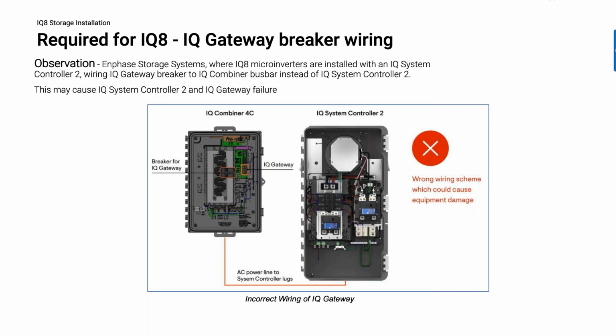What happens is installers are very familiar with installing IQ Gateway and wiring the IQ Gateway from this bus here. All right, and this is the IQ Combiner bus. And one would think, okay, well, the IQ Combiner bus is actually connected into the system controller where I get AC. So why can't I just continue to power the gateway from this bus, because I'm getting AC here? What we're telling you is that you really need to move the power, not powered off of this combiner bus. It must be powered off of the bus that's in the system controller.